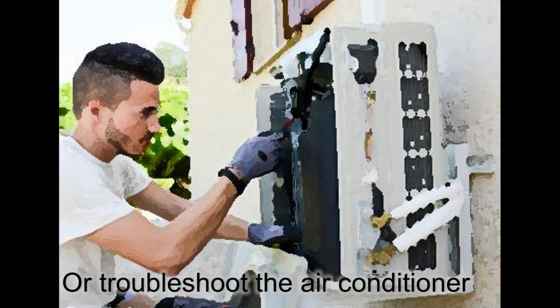If it's a bigger unit, 18,000 and above, even 12,000 and above, put it on a stand, on a snow stand. If it's a small unit, 9,000, if you put it on a wall, you may not hear the vibration, depending on structure to structure. But keep it above ground, depending on where you are. Follow your local code, because in some areas over here, some are 24 inches above the ground, 2 feet. Some are 1 foot above the ground, depending on how much snow you get on average in a year.